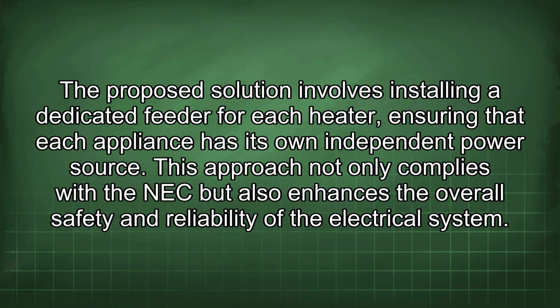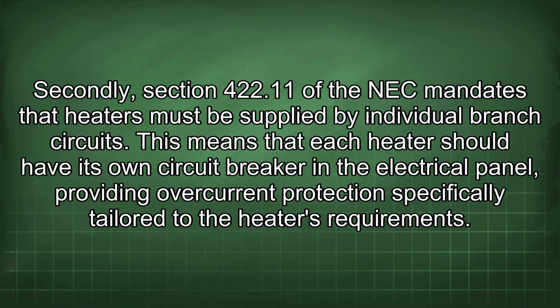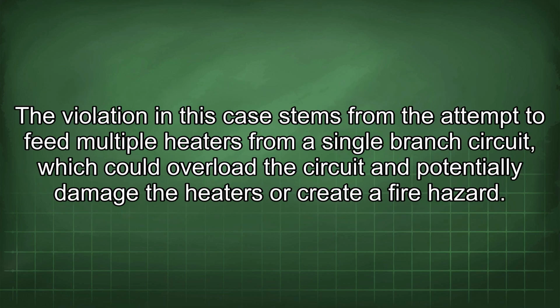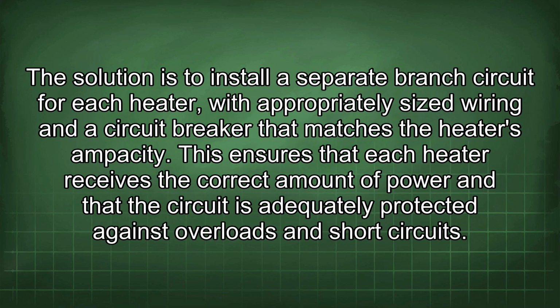Secondly, Section 422.11 of the NEC mandates that heaters must be supplied by individual branch circuits. This means that each heater should have its own circuit breaker in the electrical panel, providing overcurrent protection specifically tailored to the heater's requirements. The violation in this case stems from the attempt to feed multiple heaters from a single branch circuit, which could overload the circuit and potentially damage the heaters or create a fire hazard. The solution is to install a separate branch circuit for each heater, with appropriately sized wiring and a circuit breaker that matches the heater's ampacity. This ensures that each heater receives the correct amount of power and that the circuit is adequately protected against overloads and short circuits.